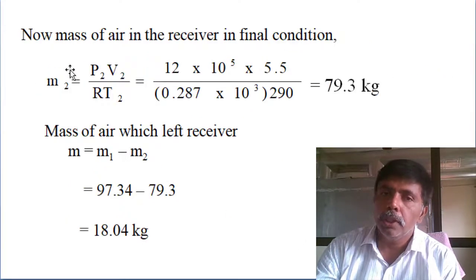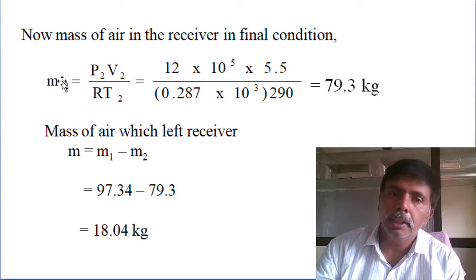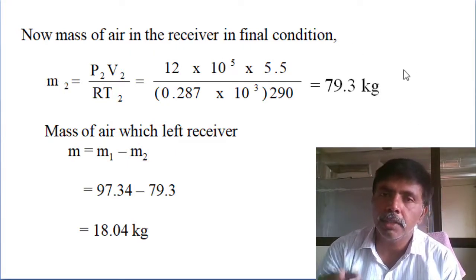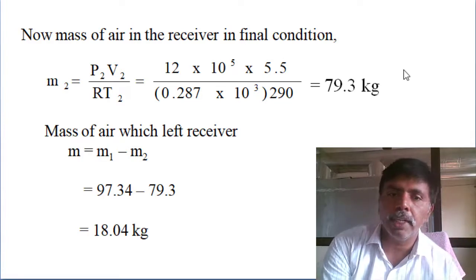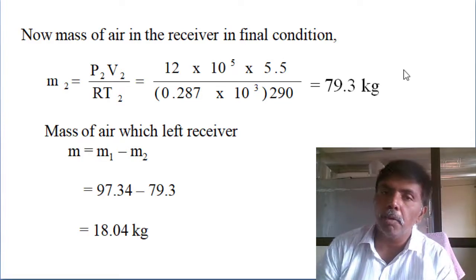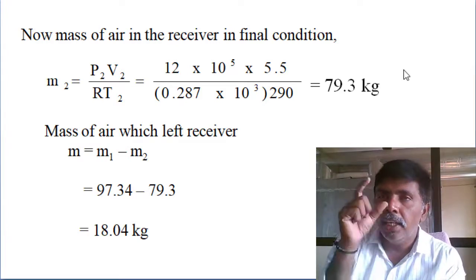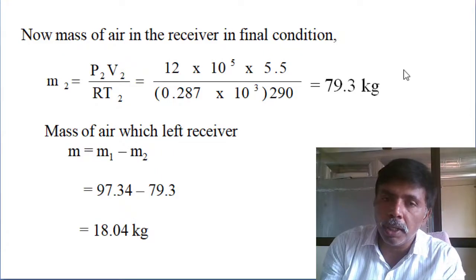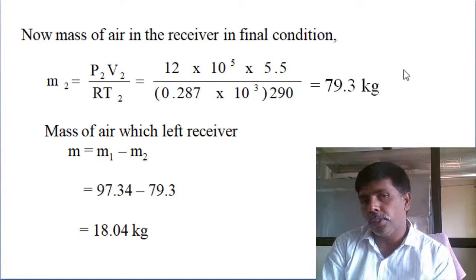Once T2 is known, use PV = mRT again to find the final mass of air, which is 79.3 kg. The initial mass was 97.34 kg. Therefore, the mass of air that left the receiver = 97.34 - 79.3 = 18 kg, which escaped while the receiver pressure dropped from 16 bar to 12 bar.